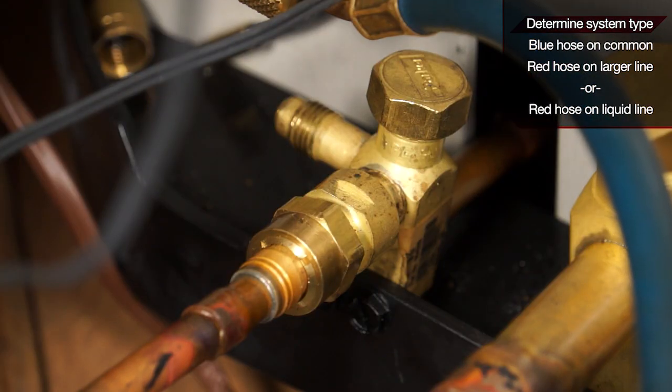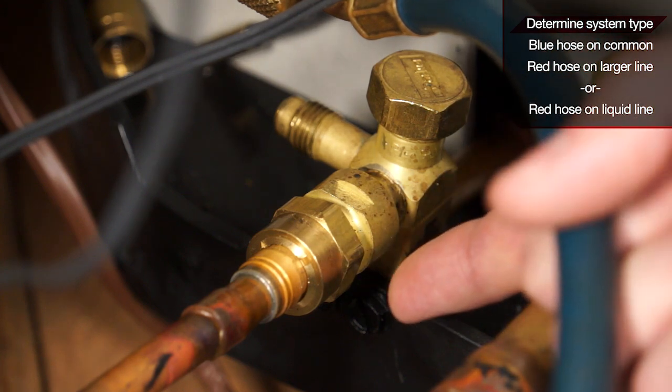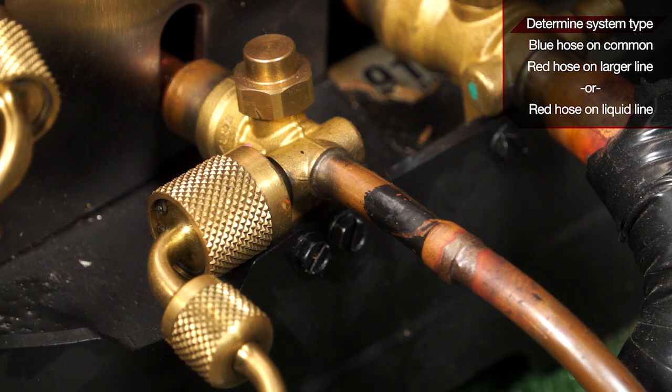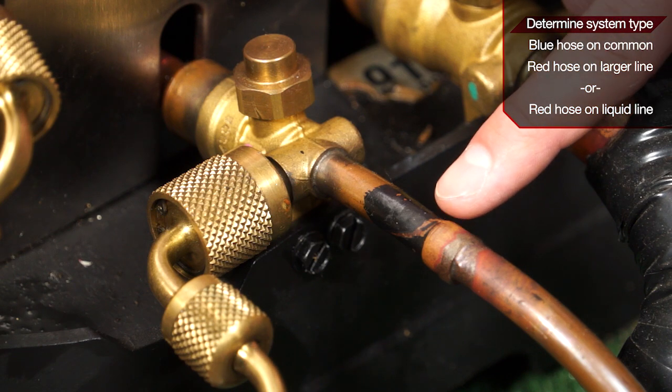First, determine if your system has a piston or a TXV. A piston driven system will have a threaded liquid line service port. With the TXV driven system, you'll have a brazed connection right at your liquid line service port.